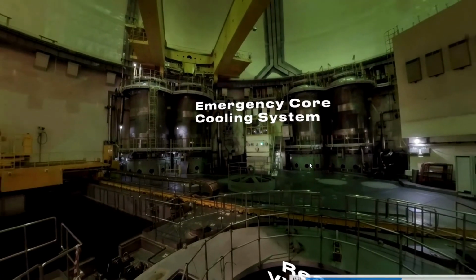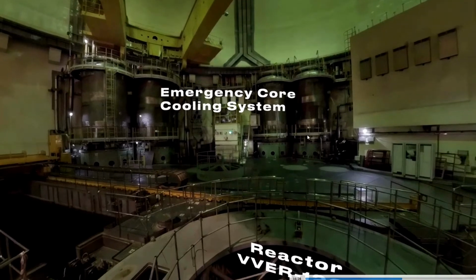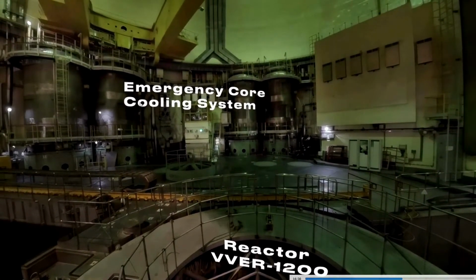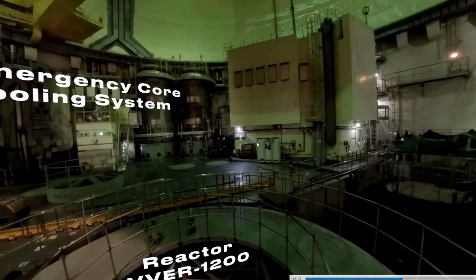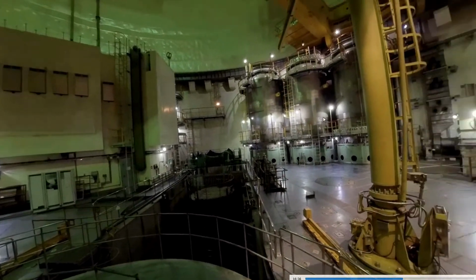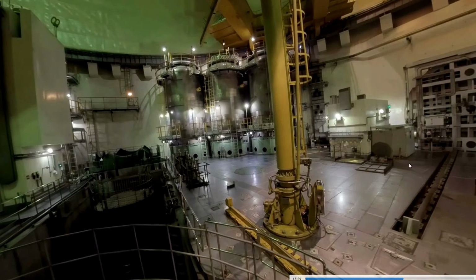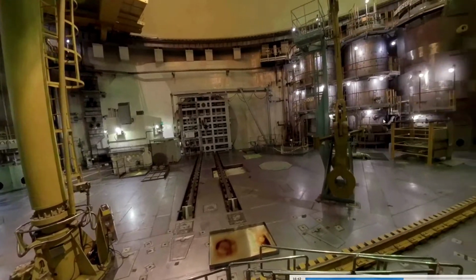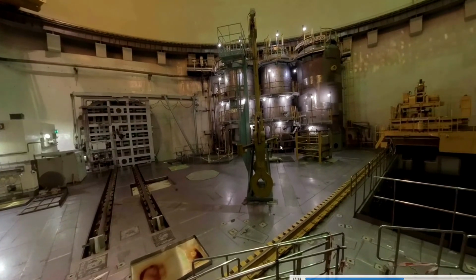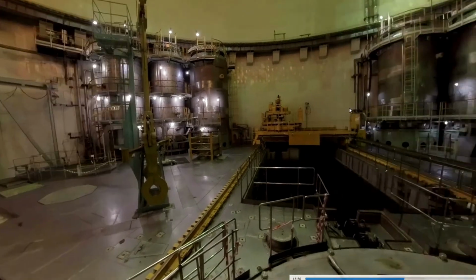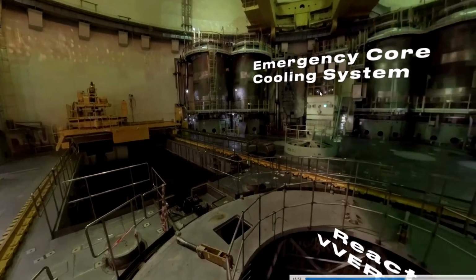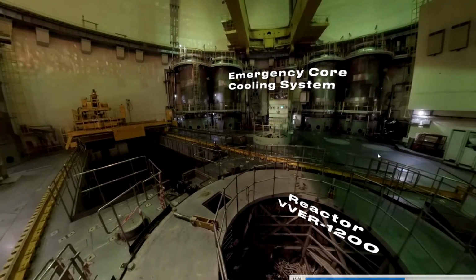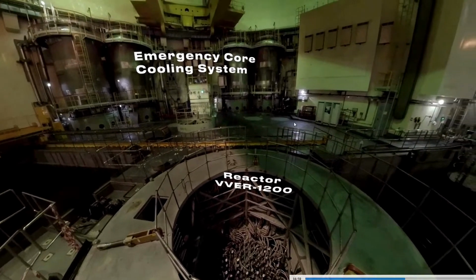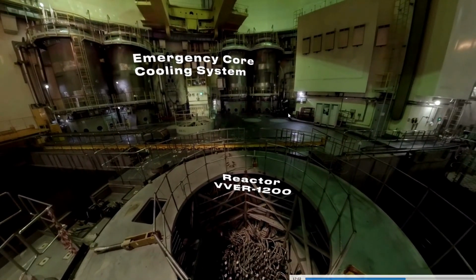And one more passive system is the emergency core cooling system. It consists of 12 tanks. We can see them around the reactor hall, surrounding the reactor hall. So there are 12 tanks filled with a boric acid water solution. You may ask what they are intended for. In case of emergency, when the pressure in the primary circuit falls below a certain value, the liquid spills to the reactor passively again, and the core is cooled.